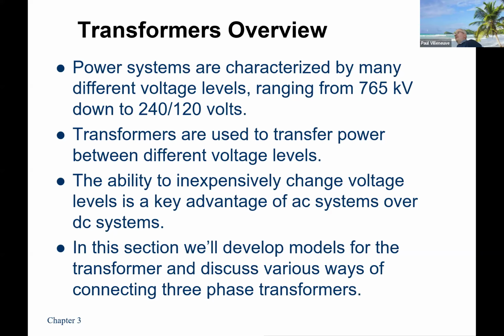No moving parts, right? That makes it pretty effortless. You do have some transformers that have fans on them for cooling, but that's just external. If it gets too hot, they'll trip the transformer offline to protect it. So yes, transformers are extremely, extremely reliable. Probably the most reliable electrical equipment that actually does something in the world. Again, no moving parts.